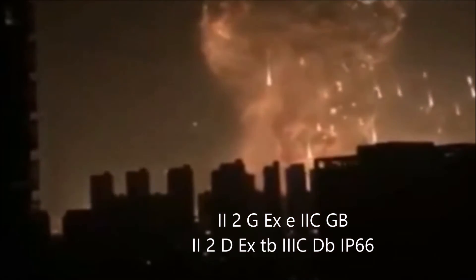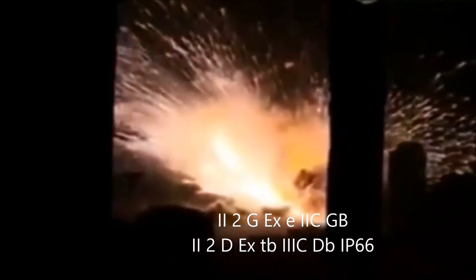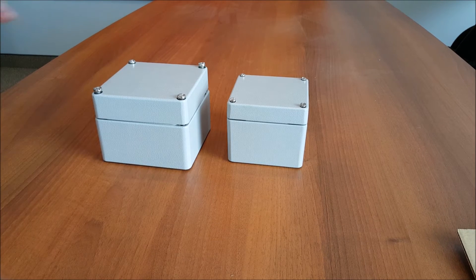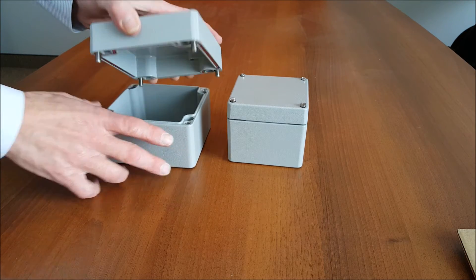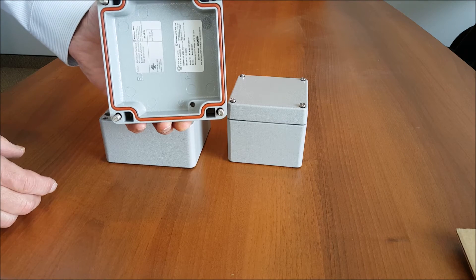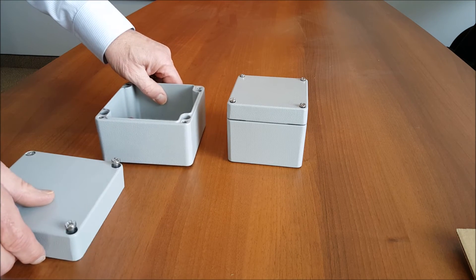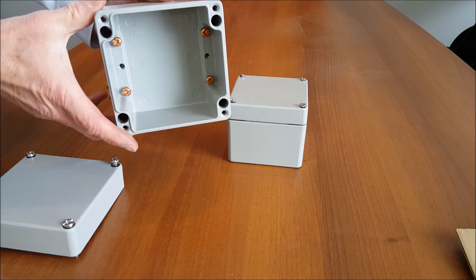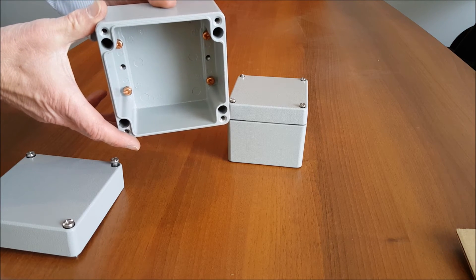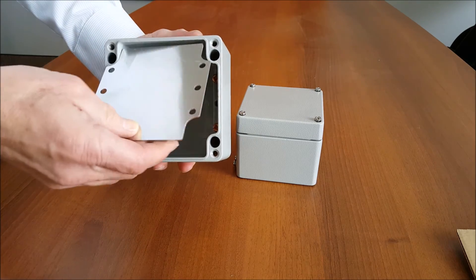Full ratings are appearing on the screen. Made from heavy-duty die cast aluminum, we have 10 sizes available to meet a variety of component needs. The product is IP66 and NEMA type 6P, providing significant water and corrosive protection. They are gray powder coated and have a service temperature range of minus 50°C to plus 135°C.